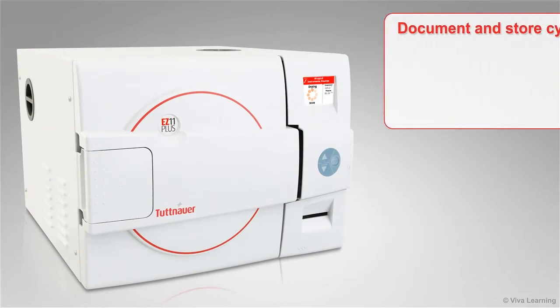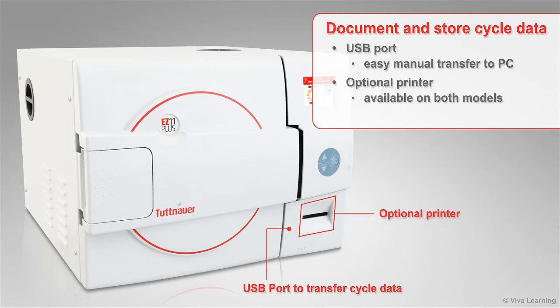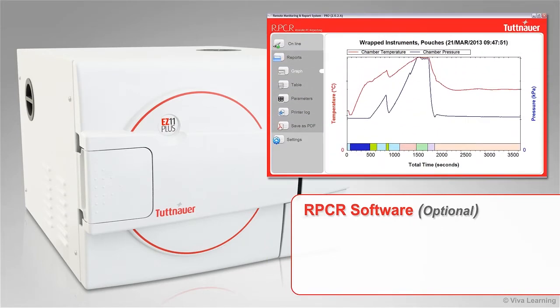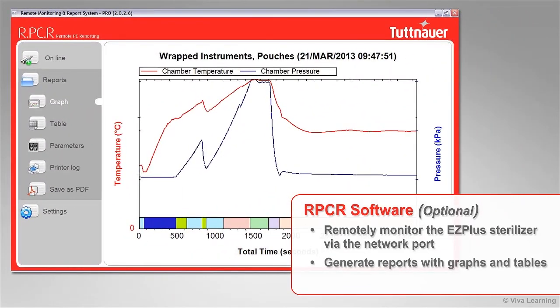If your office requires documenting and storing cycle data, it can be easily transferred manually to a PC from the USB port. An optional printer is available on both models to provide a hard copy of cycle data when required. Additionally, when using Tuttnauer's optional RPCR software, users can remotely monitor the EZ Plus sterilizer on their local network via the unit's network port. The RPCR software can generate reports with graphs and tables that can be saved as a PDF file.